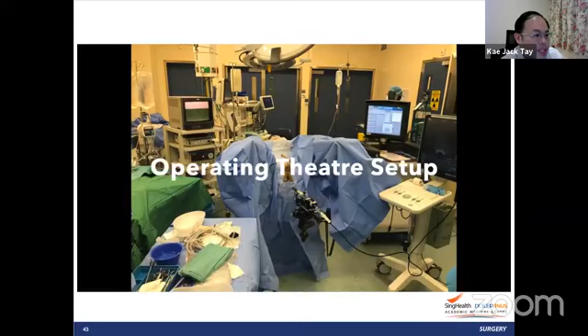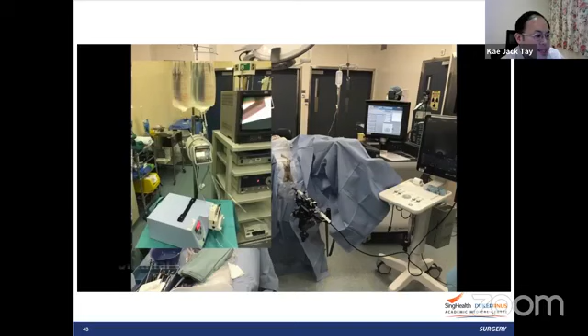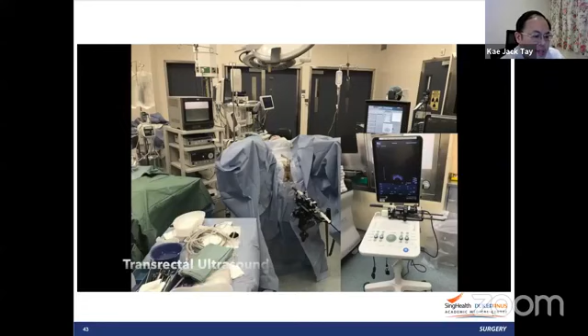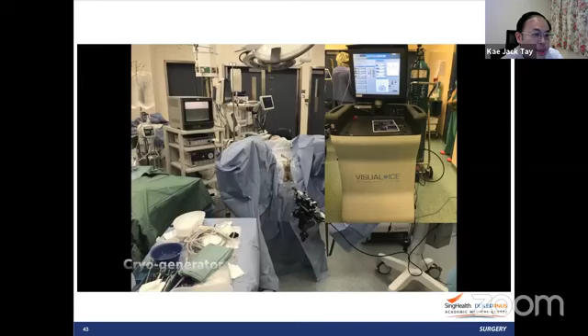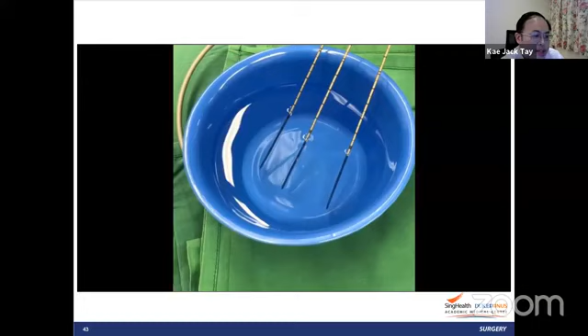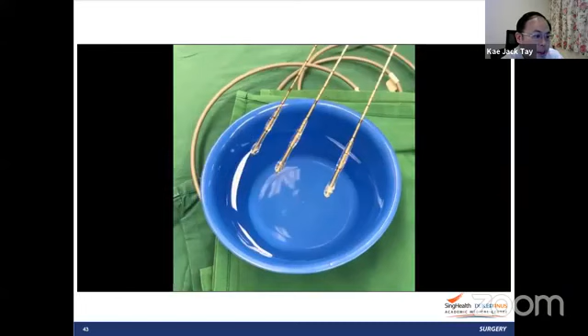So this was our setup, how we set up our operating theater. Patients in lithotomy position. We have that biplanar ultrasound probe there under general anesthesia. There's a urethral warming catheter, which is important to protect the urethra. Transrectal ultrasound. And this is the cryotherapy machine, Visual-ICE system with the argon gas. And here we are testing the cryoprobes before we put it into the patient to check for any air embolisms. It's important to test this before you put it into the patient. And you can see the freeze and thaw there is working well.